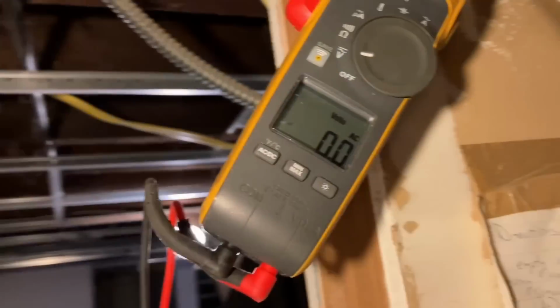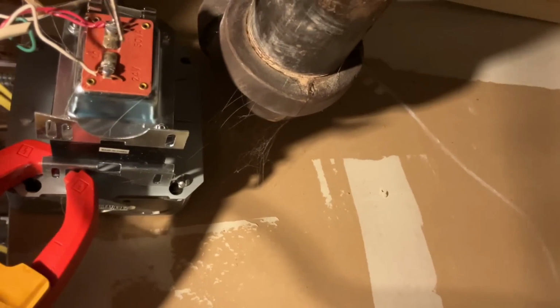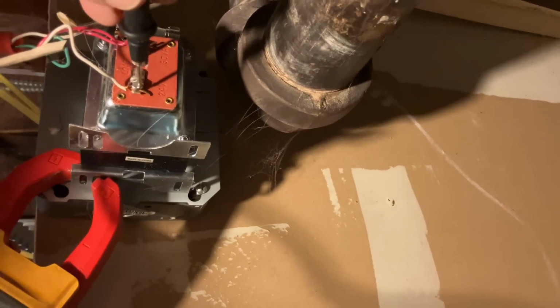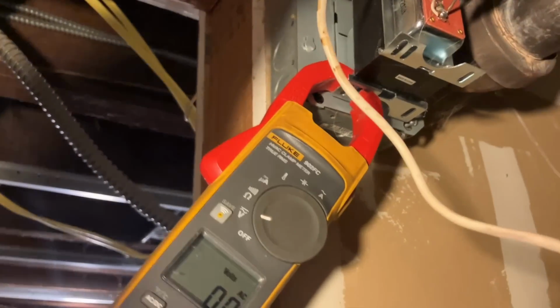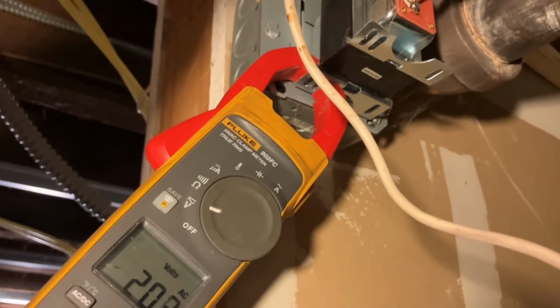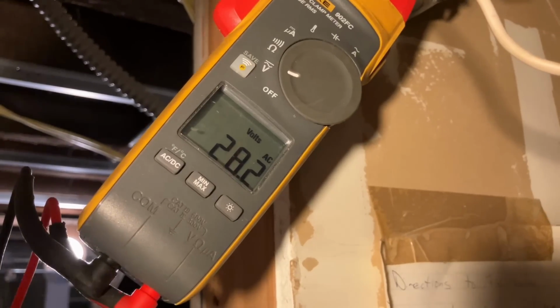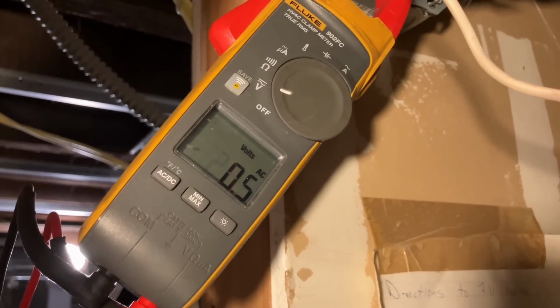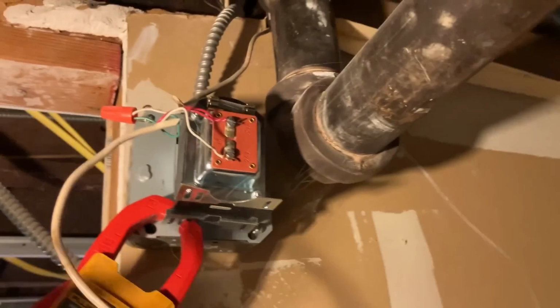Let's make sure we have no power. There's our voltmeter. Let's check for 24 volts at this transformer. There's none there. You want to turn that switch back on for a second? The homeowner is going to turn the switch back on. And we have 28 volts. Cool, turn it off. Please leave it off. This is the only power going to the boiler. So now we're good. We're going to turn off the gas like that, and let's get to work.